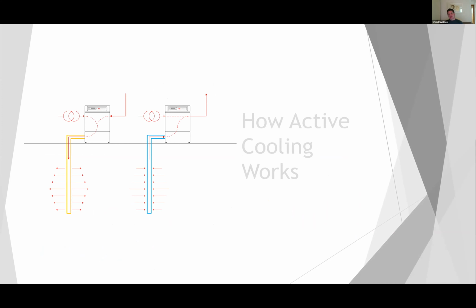Okay, so in most instances, when you've got a simultaneous heat pump, it'll have a pair of hot connections and a pair of cold connections for your heating and cooling circuits respectively. And then the ground loop will be connected to either the hot circuit if we've got too much heat, or the cold circuit if we haven't got enough heat in the system. So that's one way of doing it, or it can all be done inside the box, inside the refrigeration circuit.